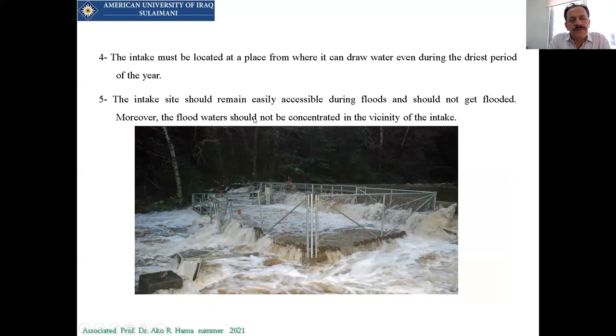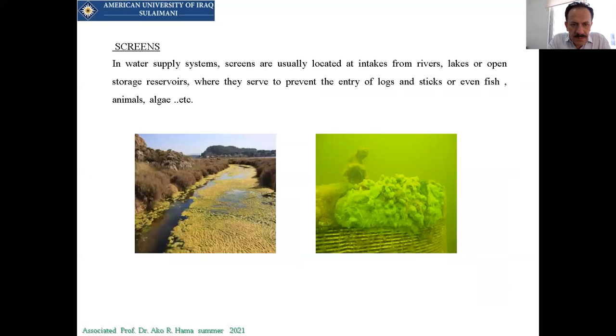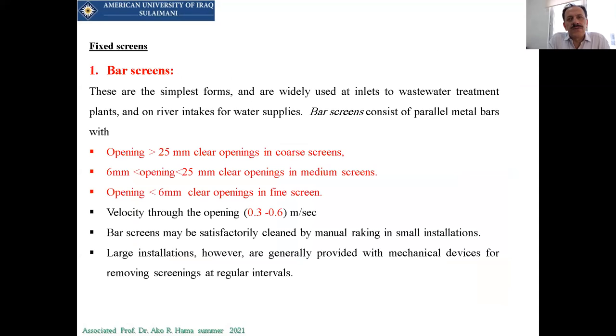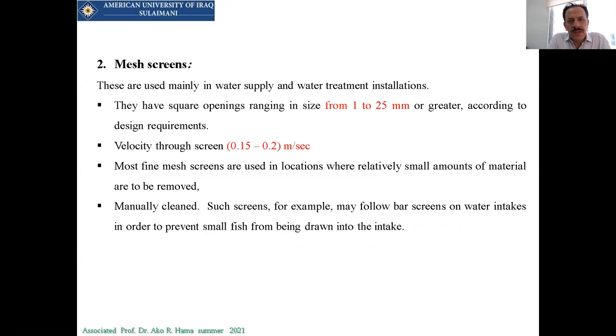We mentioned there are specific conditions to select which kind of intake to use. Most importantly, for each intake we should have screens, and we have three types: bar screens. In the bar screen we have fine, coarse, and medium, depending on the space between the bars. More than 25 millimeters is considered coarse, less than 0.6 centimeters is fine, and in the middle it is medium.